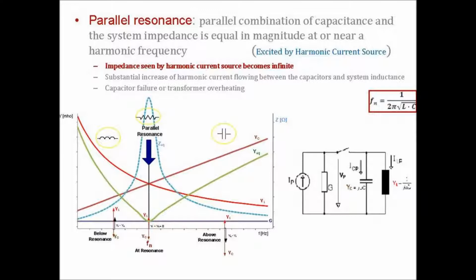So just to plot that, the admittance of the inductor decreases with frequency. The admittance of the capacitor increases with frequency, and I've got conductance there as well. When the two of them collide, the admittance of the equivalent circuit becomes quite low. But everybody knows that the admittance is the inverse of the impedance. And when the admittance is low, the impedance is high. And it becomes quite close to infinity. The only thing that's limiting it is that G at the bottom there. So the resistance basically is limiting how high the impedance gets in the system. So if you have a current that interacts and falls at Fn, which is the frequency of the harmonic resonance there, what will happen is you'll have a significant distortion in the system, which is not good.